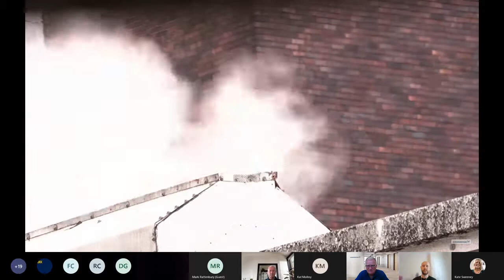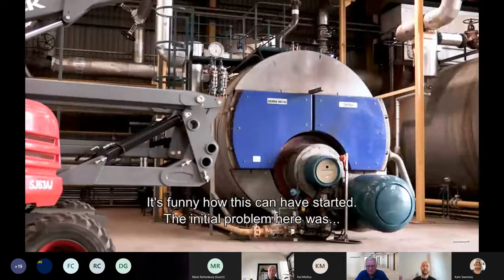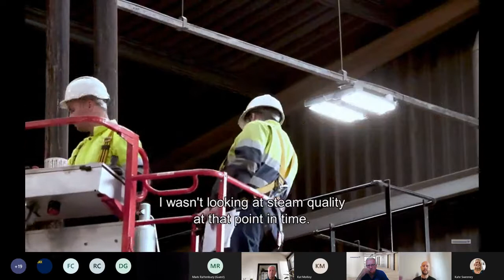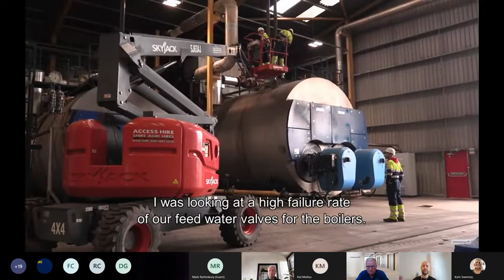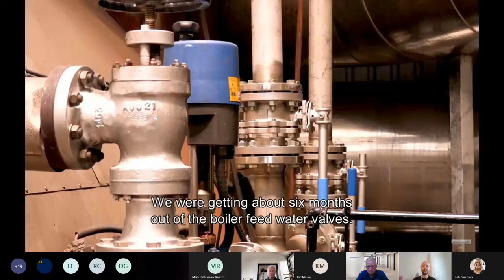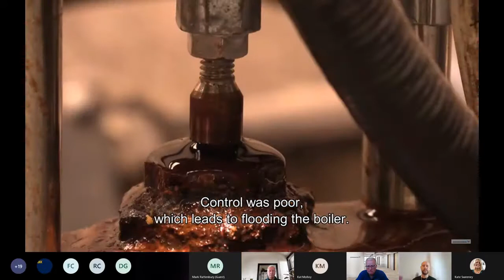So anything we can do to cure that at the root cause rather than out in the field is a plus. It's funny how this started. The initial problem wasn't steam quality - I was looking at a high failure rate on our feed water valves for the boilers. We were getting maybe 6 months out of the boiler feed water valves. Control was poor, which leads to flooding of the boiler.